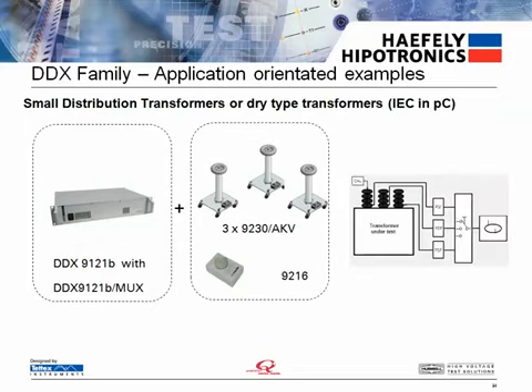When testing small distribution transformers, we'll provide a DDX9121B with a multiplexer option. With 3 coupling capacitors, the user can switch between the 3 phases of the transformer and a 9216 as the calibrator.